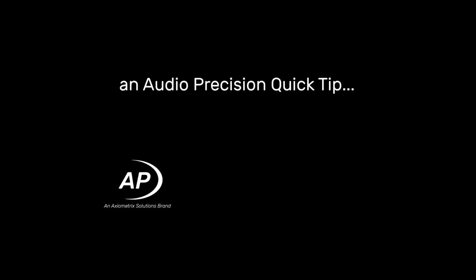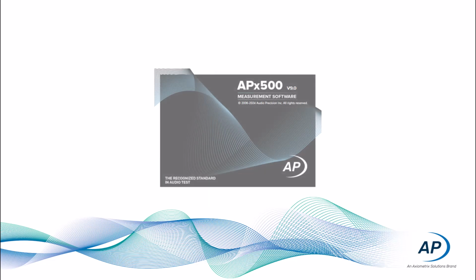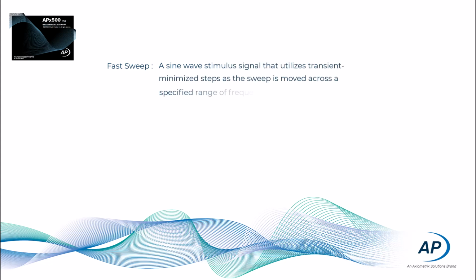Quick tips provide a brief look at an APx500 feature or function. This quick tip explains fast sweep enhancements in APx500 version 9.0. The APx500 fast sweep signal is a sine wave stimulus that utilizes transient minimized steps as a sweep is moved across a specified range of frequencies.